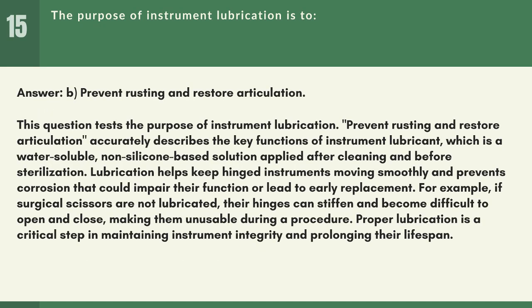Answer: B. Prevent rusting and restore articulation. This question tests the purpose of instrument lubrication. Prevent rusting and restore articulation accurately describes the key functions of instrument lubricant, which is a water-soluble, non-silicone-based solution applied after cleaning and before sterilization. Lubrication helps keep hinged instruments moving smoothly and prevents corrosion that could impair their function or lead to early replacement.